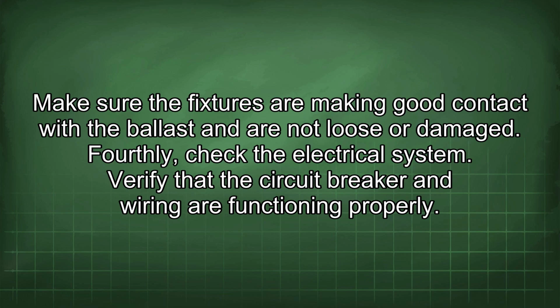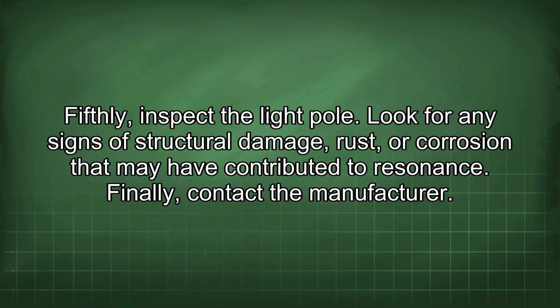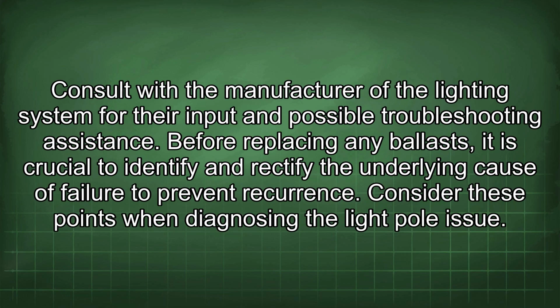Fourthly, check the electrical system. Verify that the circuit breaker and wiring are functioning properly. Fifthly, inspect the light pole. Look for any signs of structural damage, rust, or corrosion that may have contributed to resonance. Finally, contact the manufacturer. Consult with the manufacturer of the lighting system for their input and possible troubleshooting assistance. Before replacing any ballast, it is crucial to identify and rectify the underlying cause of failure to prevent recurrence.